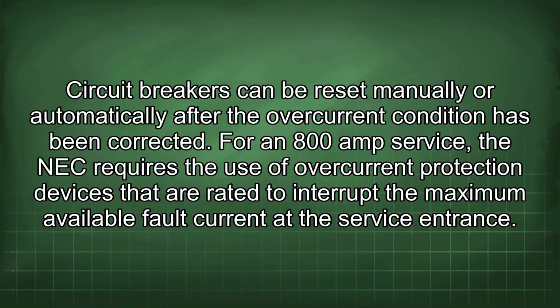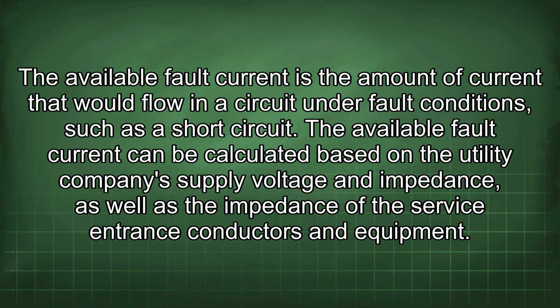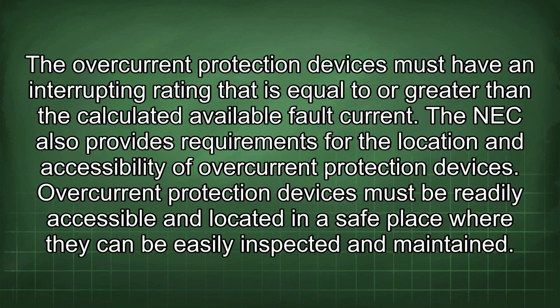For an 800 amp service, the NEC requires the use of overcurrent protection devices that are rated to interrupt the maximum available fault current at the service entrance. The available fault current is the amount of current that would flow in a circuit under fault conditions such as a short circuit. The available fault current can be calculated based on the utility company's supply voltage and impedance, as well as the impedance of the service entrance conductors and equipment. The overcurrent protection devices must have an interrupting rating that is equal to or greater than the calculated available fault current. The NEC also provides requirements for the location and accessibility of overcurrent protection devices.